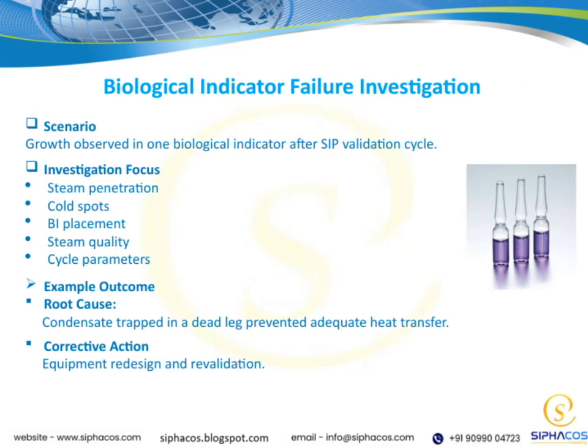Let's look at what happens when a biological indicator shows growth after a steam-in-place validation cycle. This signals a failure, and we need to dig into why. Our investigation focuses on steam penetration, cold spots, where the indicator was placed, steam quality, and the cycle parameters. In one example, the root cause was condensate trapped in a dead leg, stopping proper heat transfer. The fix? Redesigning the equipment and running a full revalidation. It's all about finding the weak spot and making it right.